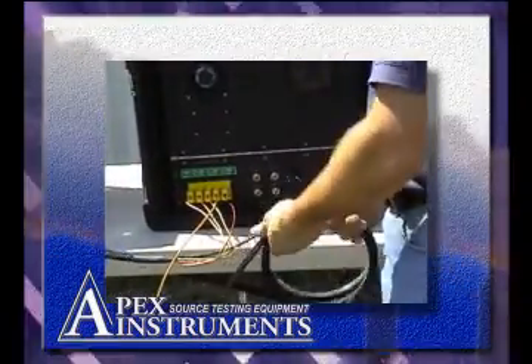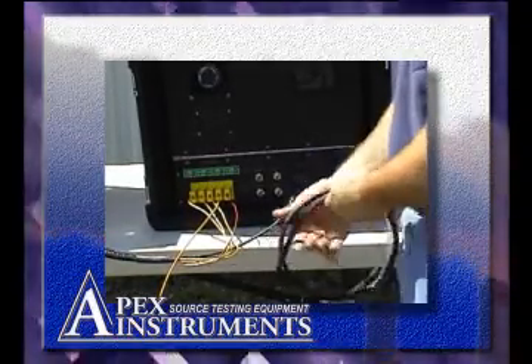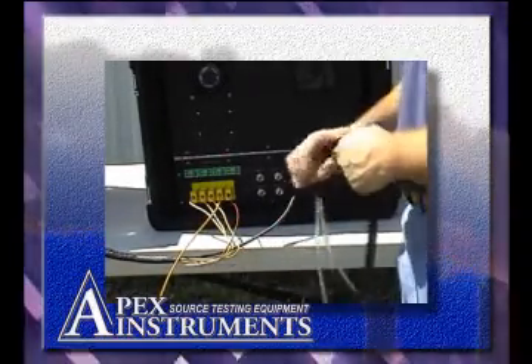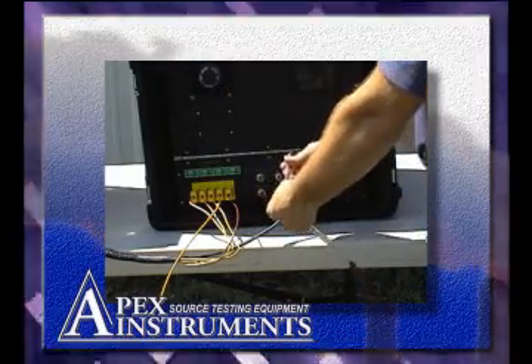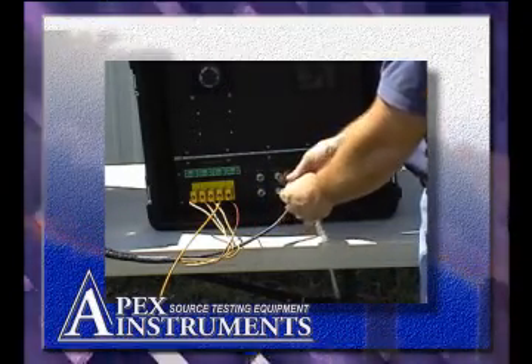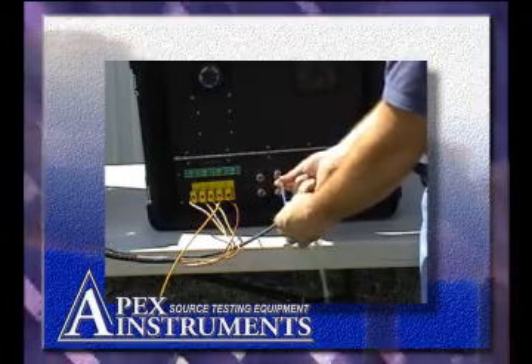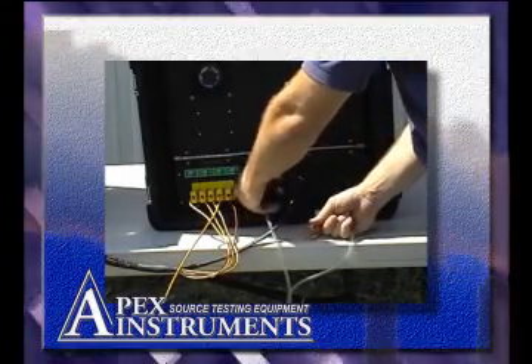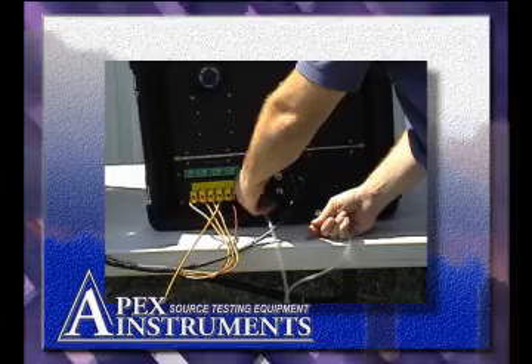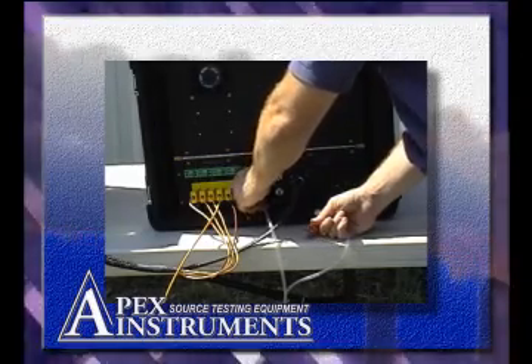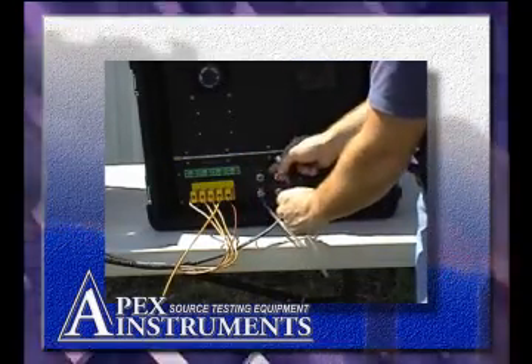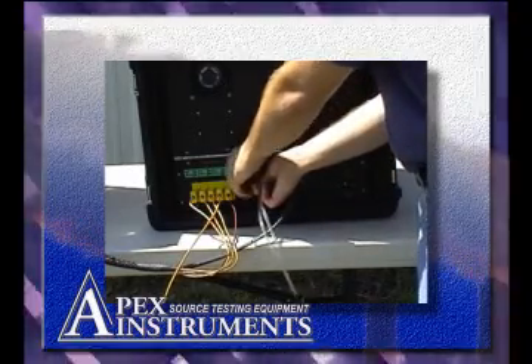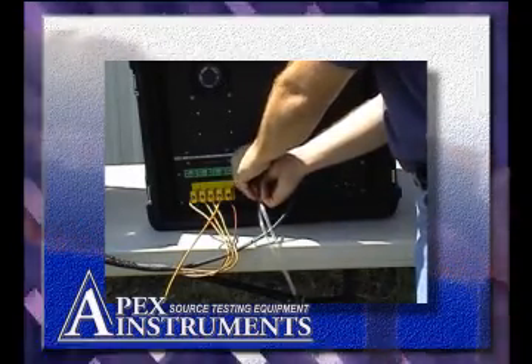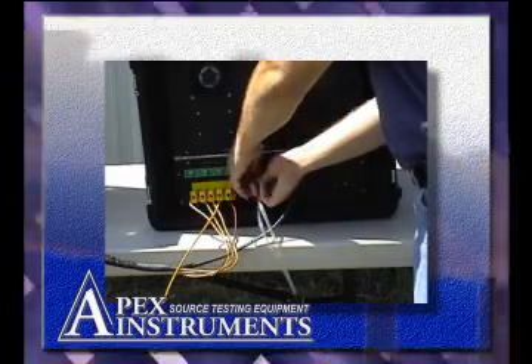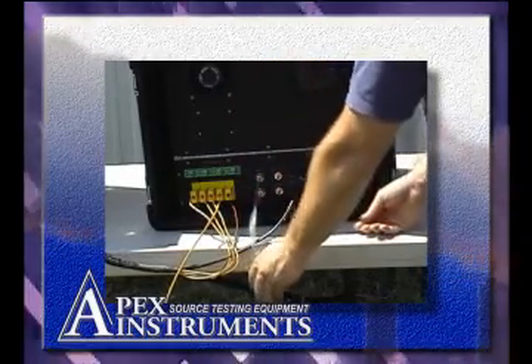Finally, the sample line jumper from the SGC-4000 should be connected to the color-coded inputs on the back of the XC-6000 console, always following the red for A, blue for B color code scheme. These connections should be finger tightened, then tightened to provide a leak-tight connection using a wrench.